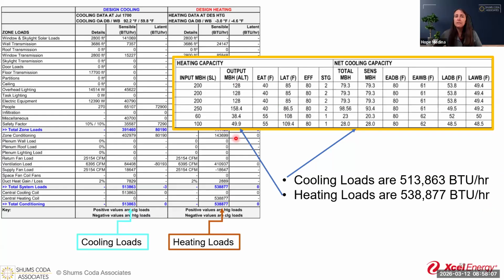So there may be times in this document, this is the total number, but if you start breaking it up by zones, which is what these are doing, maybe the output the zone needed to be 125,000, and this one is showing 128. That's comparable. That works.